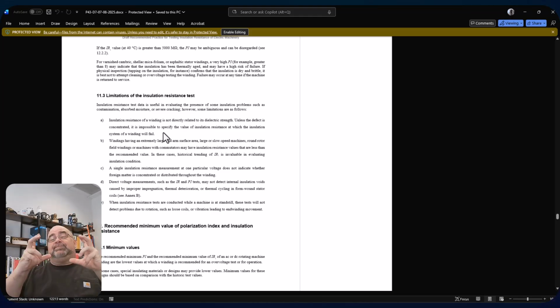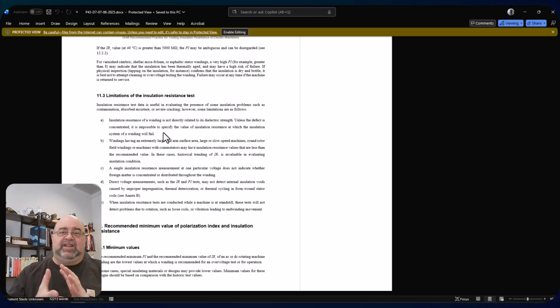So that is my pushback when I keep seeing these people saying, oh, well, at 100 megohms, that's when we replace the stator. Why? What I would say is, okay, you've hit that point, and by the way, for a low or high voltage motor at 100 megohms, you can go ahead and perform the other tests to see if this is an actual condition. Why not perform an insulation resistance profile to see what's going on with the machine? But no, people are going to condemn perfectly good machines for this, right?